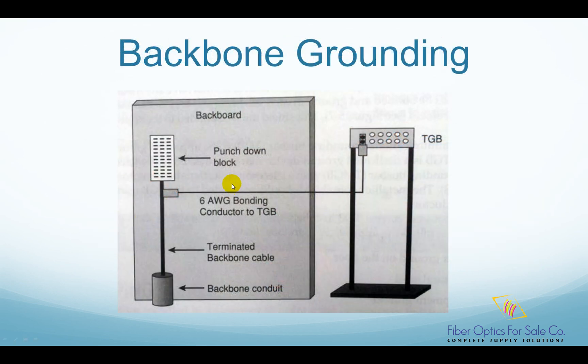Copper cables and optical fiber cables that have any metallic elements must be bonded and grounded in each telecom room. As shown in this picture, a multi-pair UTP cable that has a metallic cable shield is bonded to a dedicated ground in the telecom room. This dedicated ground device is called a telecommunications grounding bus bar, or TGB. The metallic cable shield should be bonded to the TGB using a 6 AWG insulated conductor. The TGB is in turn connected to the telecommunications main grounding bus bar.